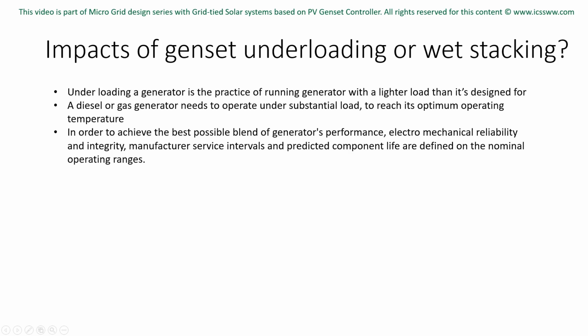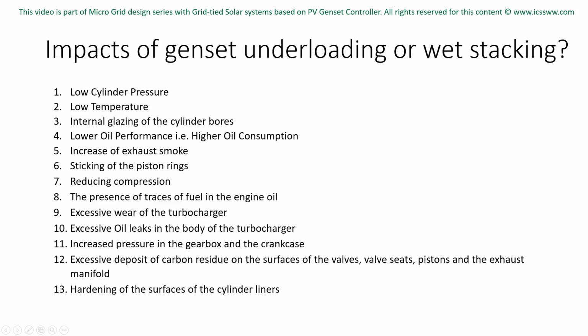What is underloading or wet stacking of a generator? Underloading a generator is the practice of running a generator with a lighter load than it is designed for. The endothermic engines that are used in generator sets have been designed to use as much power as possible, from 30 to 100% of the declared maximum power. A diesel engine needs to operate under substantial load to reach its optimum operating temperature. If it fails to reach this temperature, then a percentage of fuel will be unburnt and a buildup of soot can occur. Following are the other repercussions of running a generator in underloaded condition.